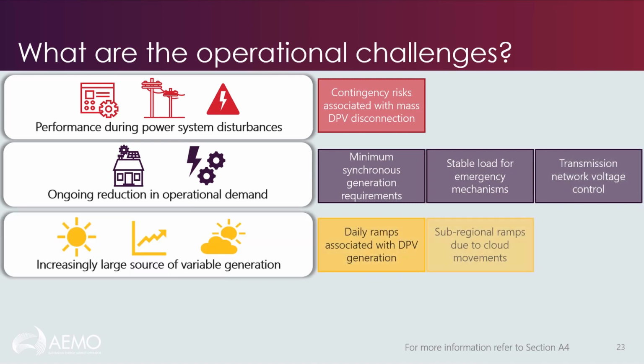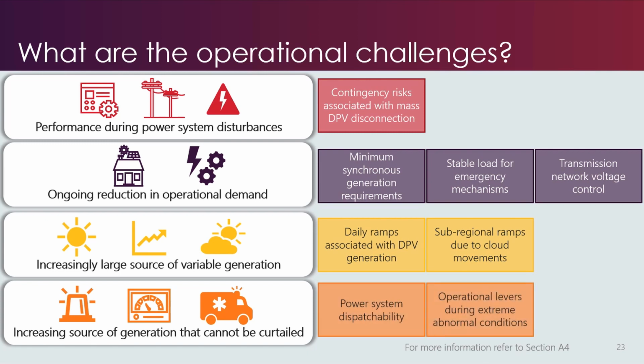The next impact to the power system is the fundamental characteristic of DPV in that it responds to solar irradiation and is therefore a variable form of generation. This means that DPV needs to be considered in the daily ramp requirements as solar comes online in the morning and goes away in the evening, and this behaviour needs to be accounted for in dispatching large generation. This can be more complicated, particularly during sudden cloud cover over a metropolitan area that can also rapidly change the ramp requirements, but also during rare events such as a solar eclipse, which would also have impacts on the ramping needs.